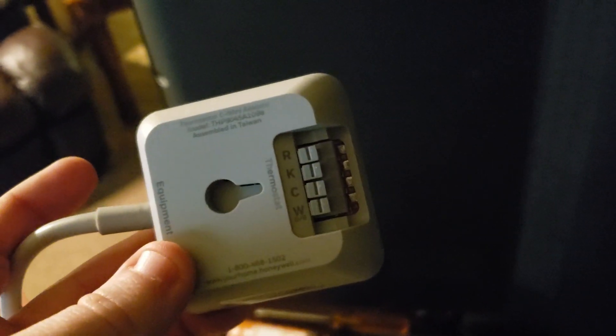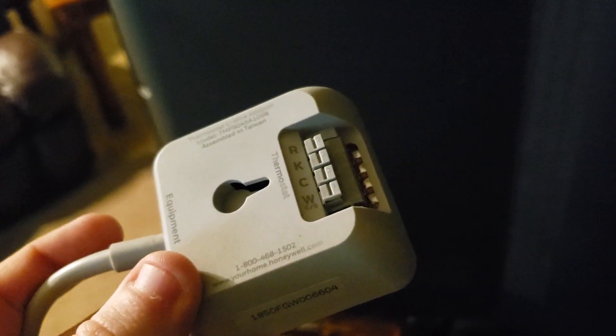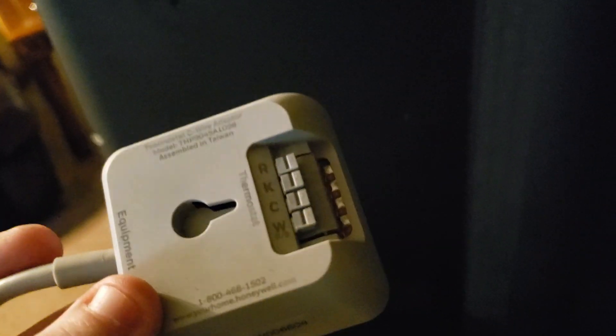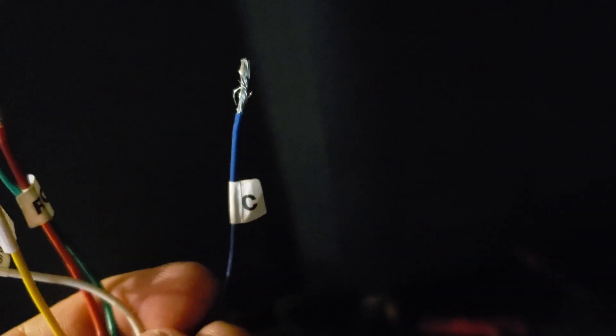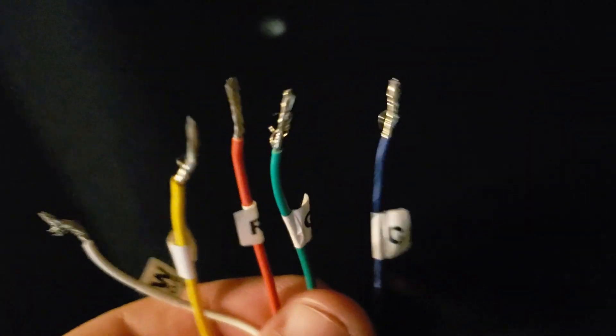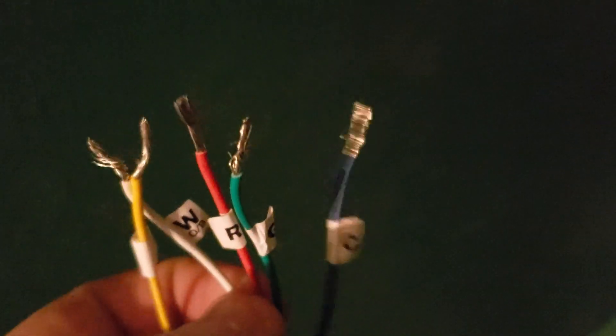On to the Honeywell C adapter. So you have R, K, C, and W. The green wire or G wire turns into C, and then the Y wire turns into K. It has a pigtail and they're all labeled, thankfully. So you got Y, W, G, R, and C. C stands for common — it's just a kind of a power source for some thermostats.